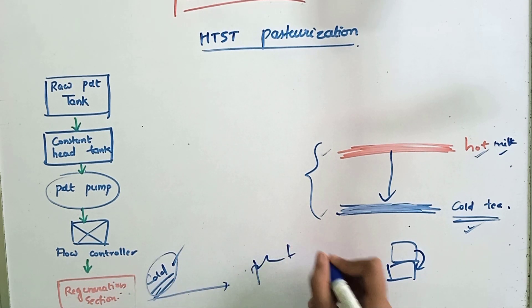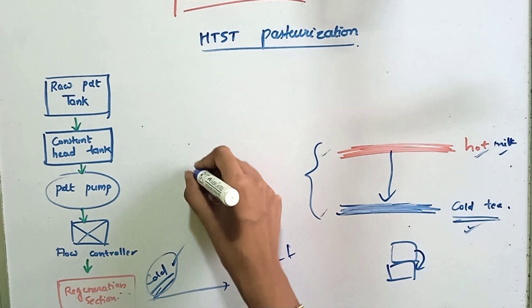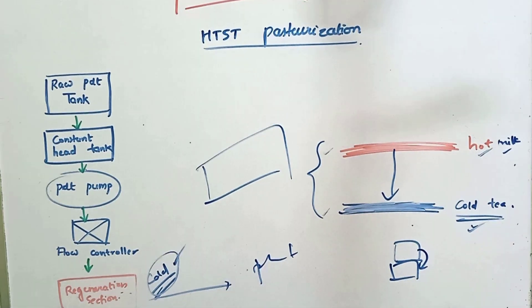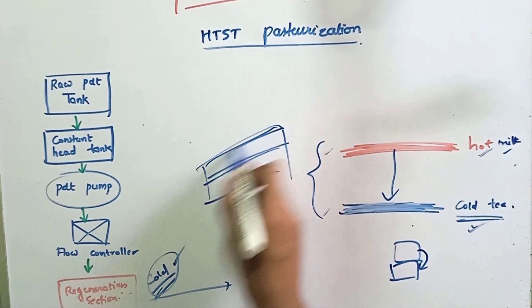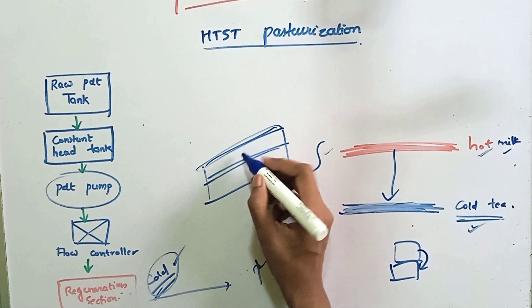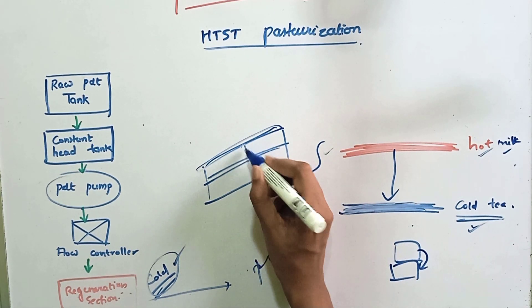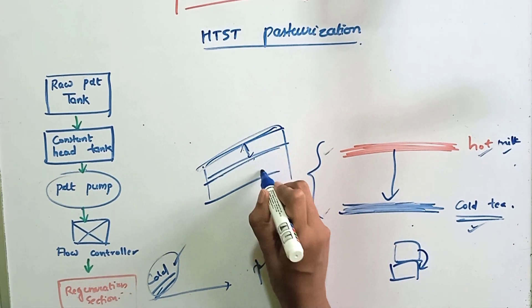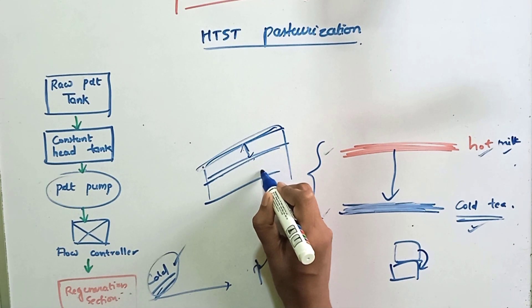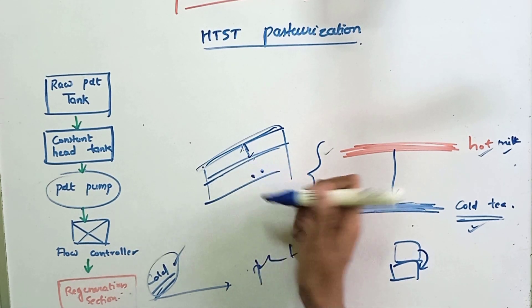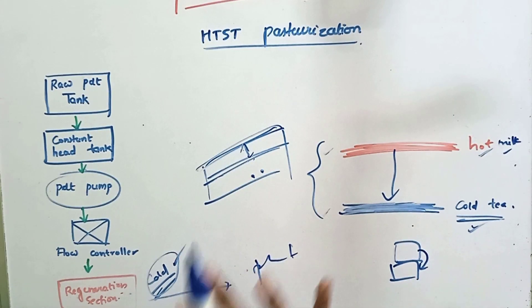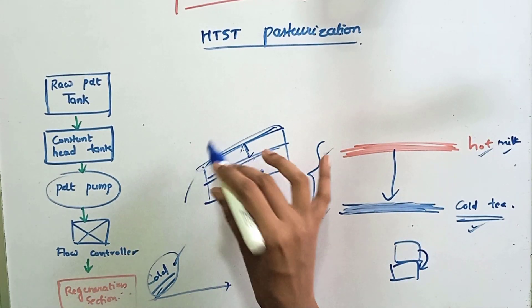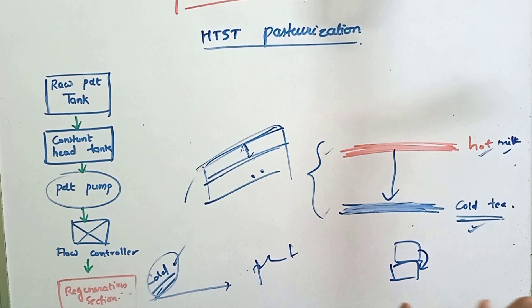In pasteurization, regeneration is carried out with the help of a plate heat exchanger. In a plate heat exchanger, a hot fluid is passed through one side of the plate and a cold fluid through the other side. The hot and cold fluids do not come in direct contact — both come in contact with the plate. Heat is transferred through the plate. In HTST pasteurization, we normally use a plate heat exchanger for the purpose of regeneration.